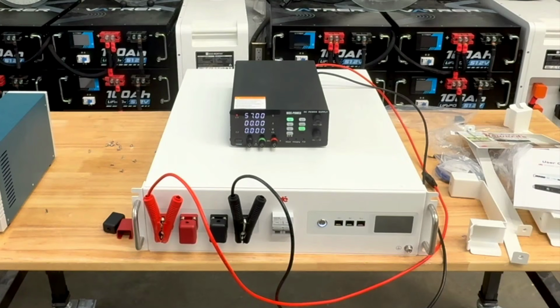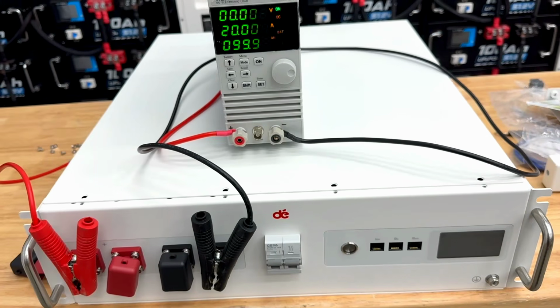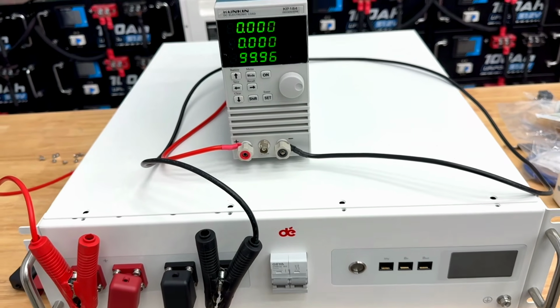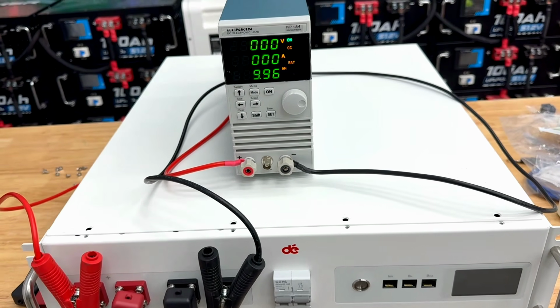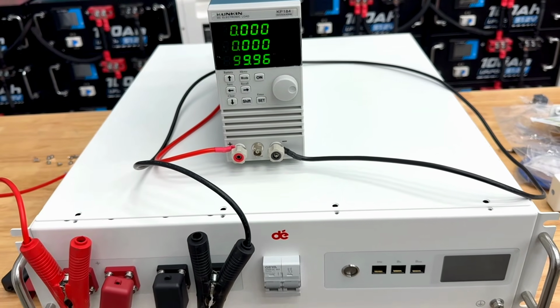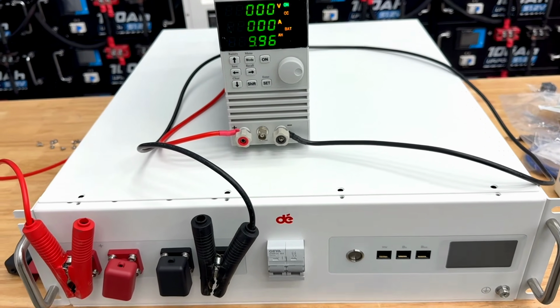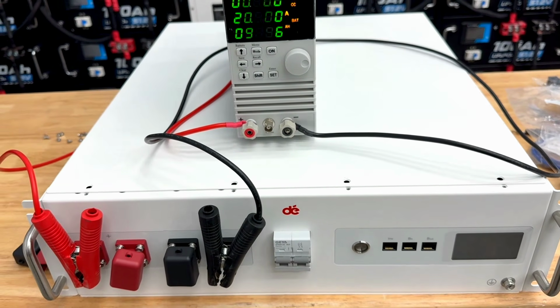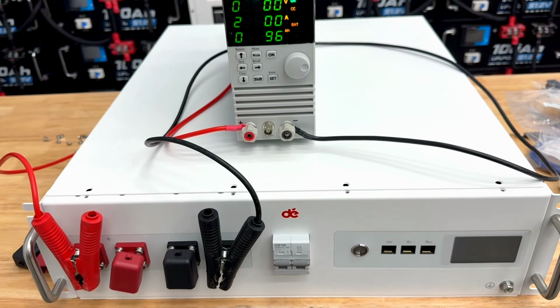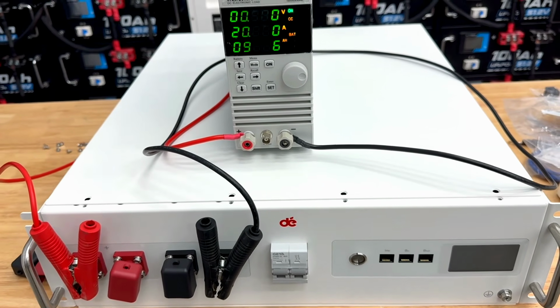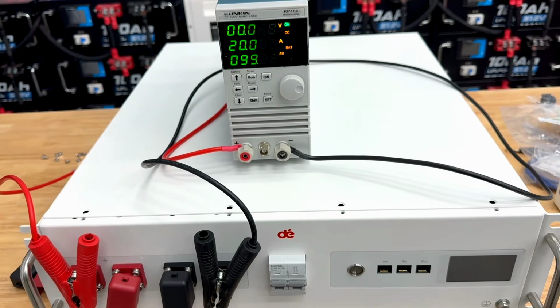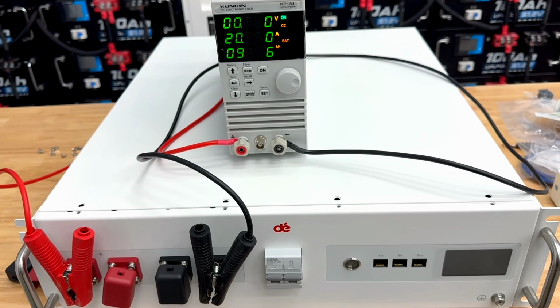Now that it's all charged up, we're going to go ahead and start the capacity test. Looking at the capacity, it ended up at 99.96, so just under 100 amp hours. This is a 100 amp hour battery, and typically I'll see anywhere from 103 to 106. So this one is definitely lower than the rest.